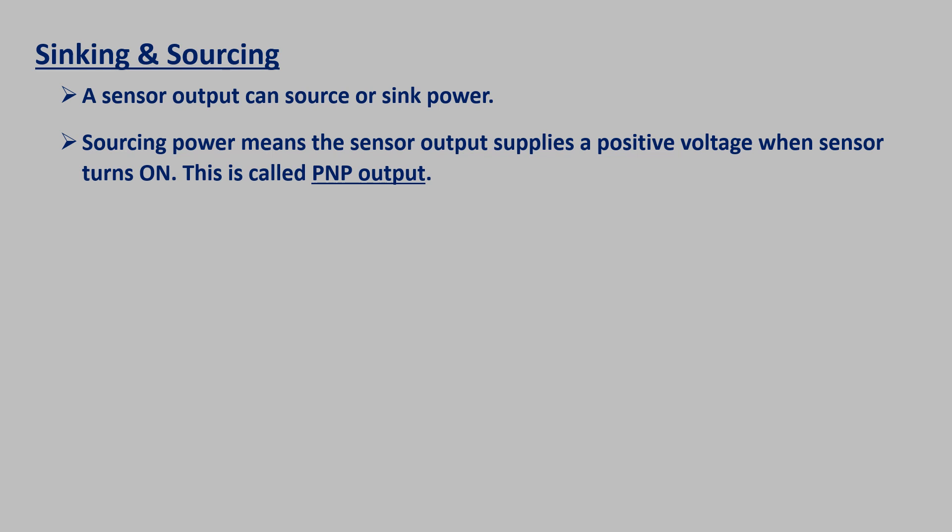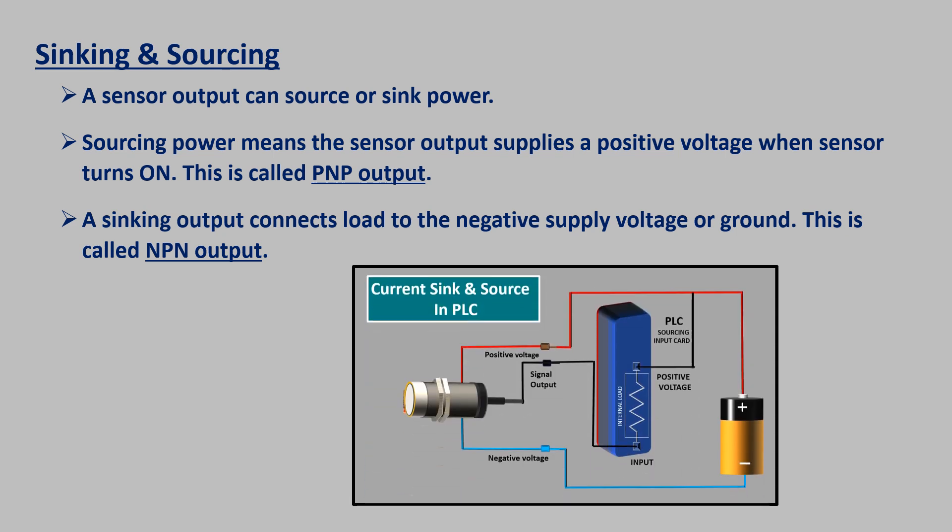Sinking and sourcing: A sensor output can source or sink power. Sourcing power means the sensor output supplies a positive voltage when the sensor turns on. This is called a PNP output. A sinking output connects the load to the negative supply voltage that is also ground in many systems. These connections are called NPN outputs. We have already discussed about sinking and sourcing concepts in a previous video. Link of that video is there in the description.